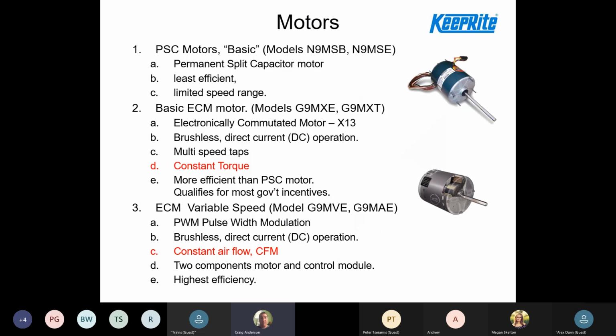So this is what we used to look at in our old furnaces. We used to have the whole PSC motor, 110 volt. That is not out there. We cannot get it in a furnace anymore, but we still have a lot of furnaces out there with them. Then we had the basic X13 motor, which was in our 2-stage and our single-stage furnaces. And then we had the variable speed constant airflow that was in our communicating furnace. So those are the 3 motors that we had before, and I just showed you the 3 that we have now.